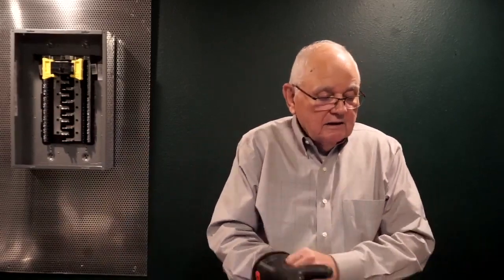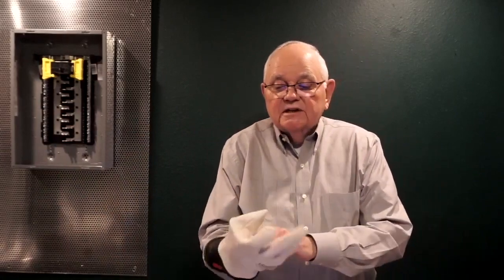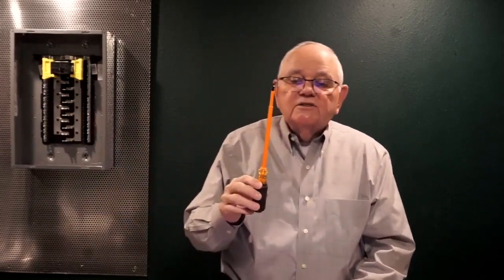So anyway, my restricted approach boundary, what that means to me is that anything I take within that restricted approach boundary has to be insulated. So if I'm going to put my hand in there, my hand's going to be insulated, isn't it? By the rubber gloves and leather protector. If I take a screwdriver in there, the screwdriver is going to be an insulated screwdriver.